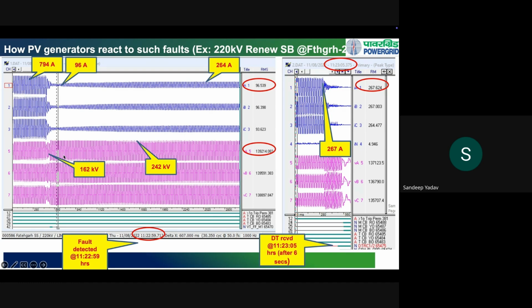So what happens is that because all the PV generators behave almost the same way, they all reduce their own active power. If all the PV generators reduce their active power, what happens is that the systems, all these 765 kV and 400 kV transmission lines, become lightly loaded. And when transmission lines are lightly loaded, they generate more reactive power than they consume.